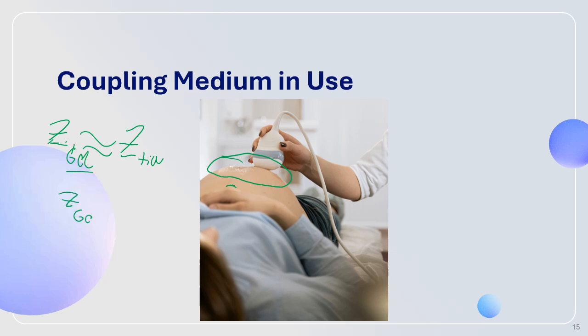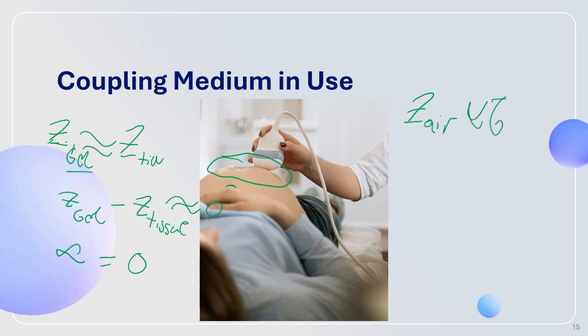So Z gel minus Z tissue will be approximately equal to 0. Therefore, alpha, the intensity reflection coefficient, will approximately be equal to 0, and then all of the incident beam will be transmitted. If we don't use the gel, the difference between the specific acoustic impedance of air and Z tissue is very large. So literally none of the incident beam will actually be transmitted through the body.